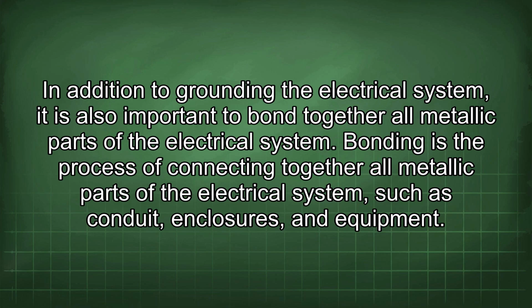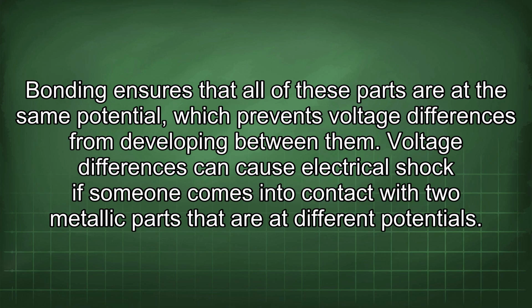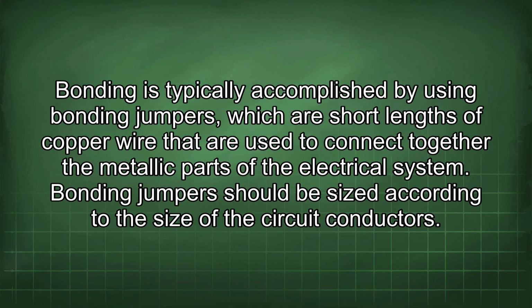In addition to grounding the electrical system, it is also important to bond together all metallic parts of the electrical system. Bonding is the process of connecting together all metallic parts of the electrical system, such as conduit, enclosures, and equipment. Bonding ensures that all of these parts are at the same potential, which prevents voltage differences from developing between them. Voltage differences can cause electrical shock if someone comes into contact with two metallic parts that are at different potentials. Bonding is typically accomplished by using bonding jumpers, which are short lengths of copper wire that are used to connect together the metallic parts of the electrical system.